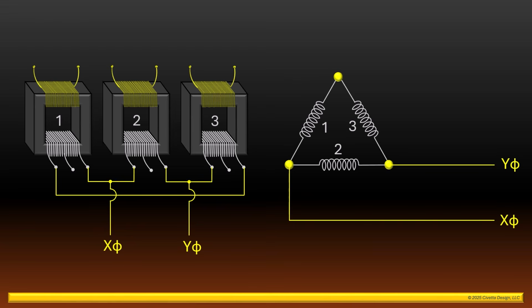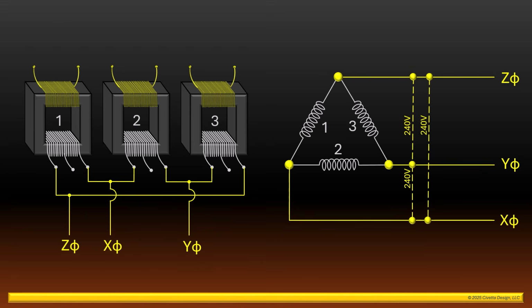Now, as we've already shown, each of these transformers produces a secondary voltage of 240 volts across the outer leads. So the voltage potential between X phase and Y phase is 240 volts. We then connect the Z phase lead to the long jumper wire. This then connects the Z phase to the Y phase through the windings of transformer number 3 and produces a voltage potential of 240 volts between those two phases. It also produces a voltage potential of 240 volts between Z and X through the windings of transformer number 1. This is the three-phase power of this transformer bank.